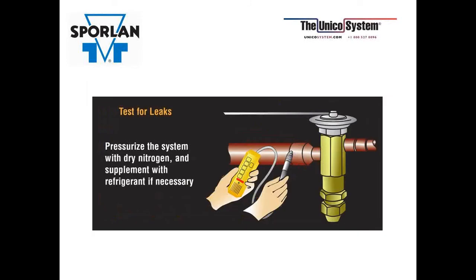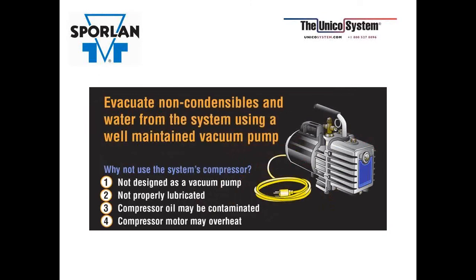Pressurize the system with dry nitrogen. If you need to, go ahead and supplement with refrigerant if necessary, and then test for leaks. Evacuate non-condensables and water from the system using a well-maintained vacuum pump.